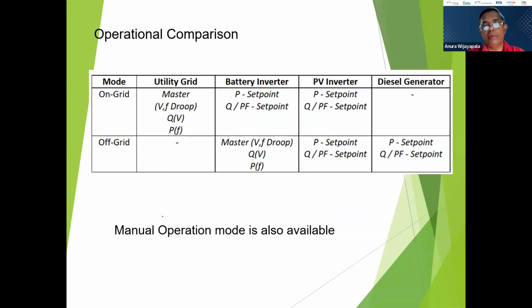And the grid will operate in different modes: on-grid and off-grid. In the on-grid mode, the utility grid will be the master in the voltage and frequency droop mode. So the battery inverter in the on-grid condition will be working on a set point of active power and the set point of Q and the power factor. And the PV inverters will be operating on a set point of power, and the Q and the power factor.